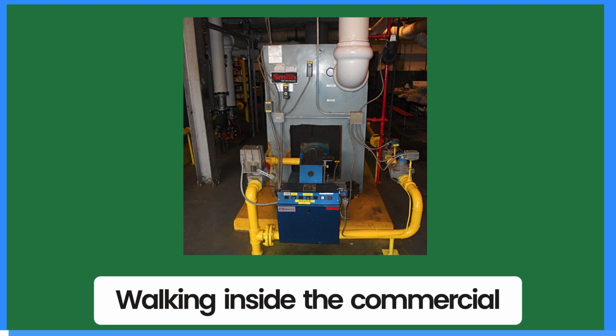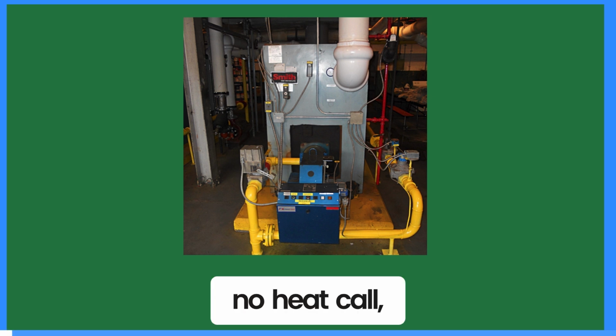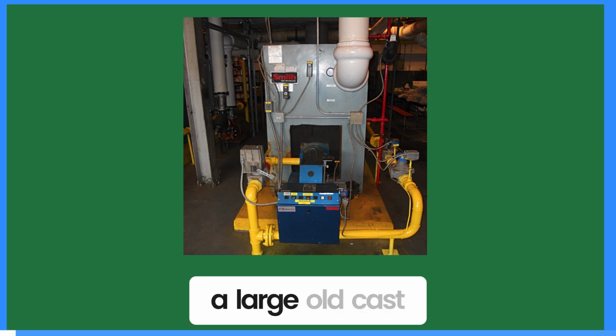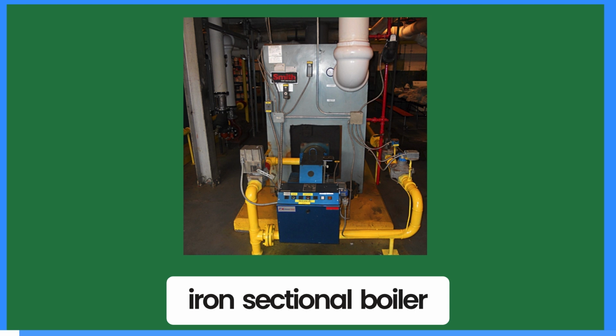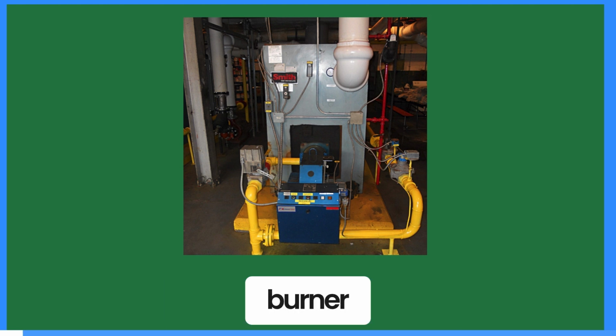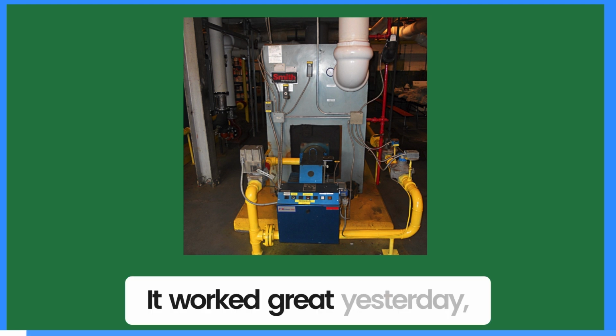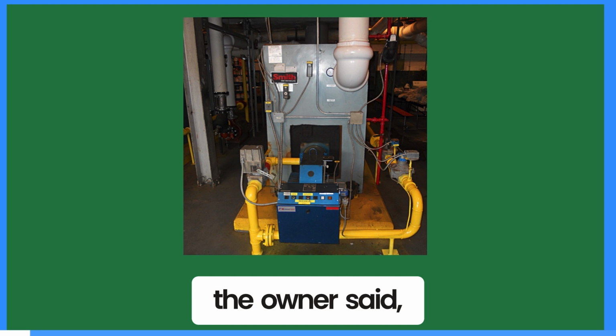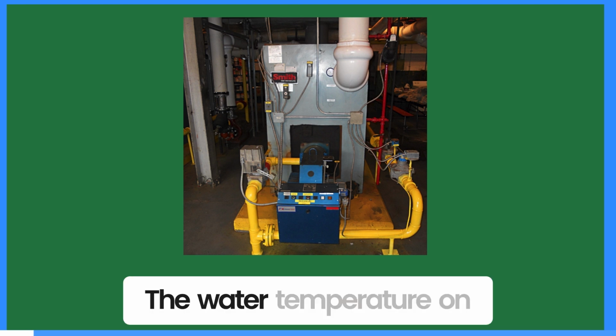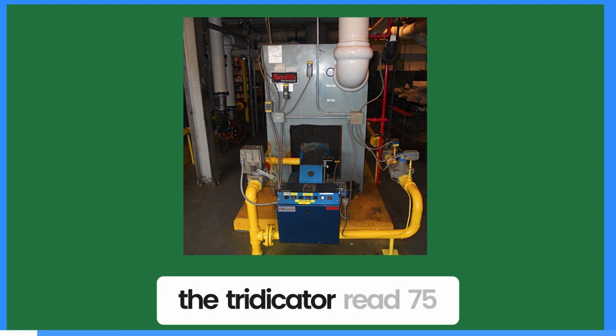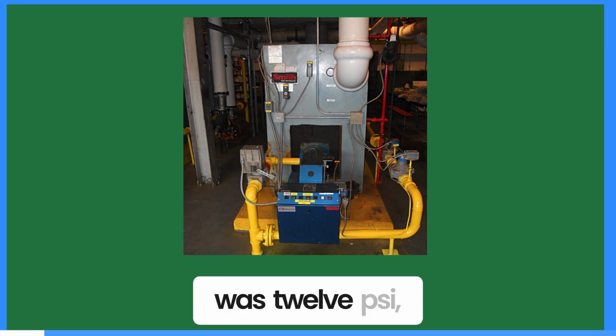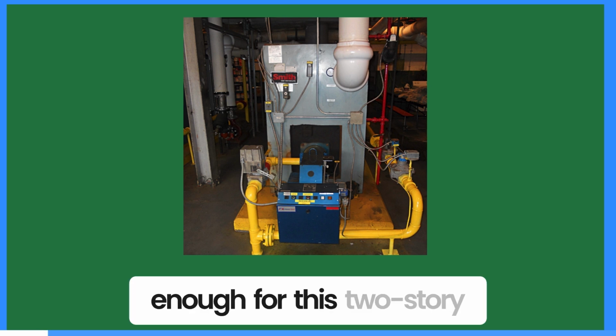Walking inside the commercial boiler room of the No Heat Call, I was greeted by a large old cast iron sectional boiler with a power flame burner. "It worked great yesterday," the owner said, and I nodded.